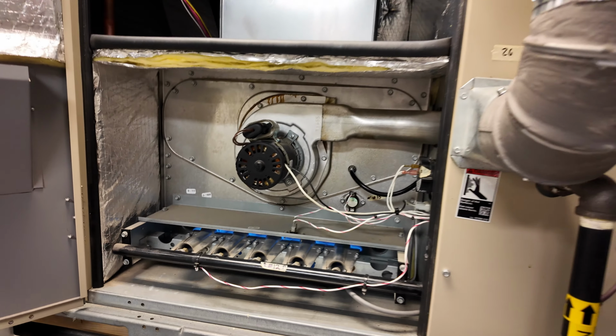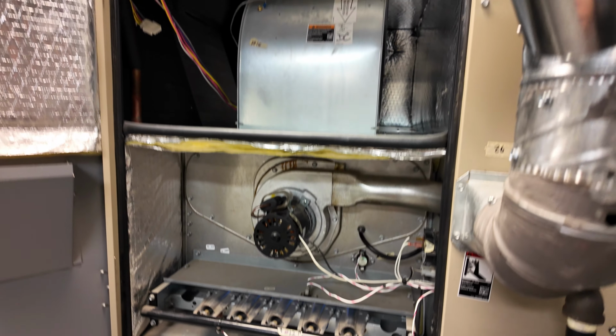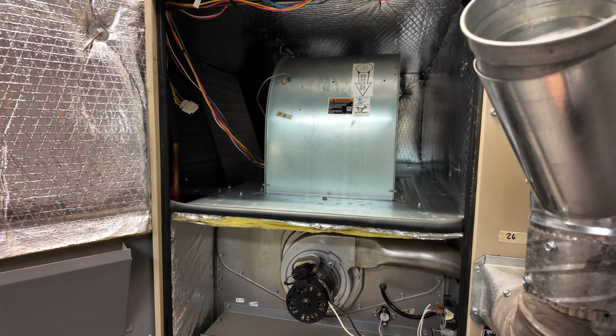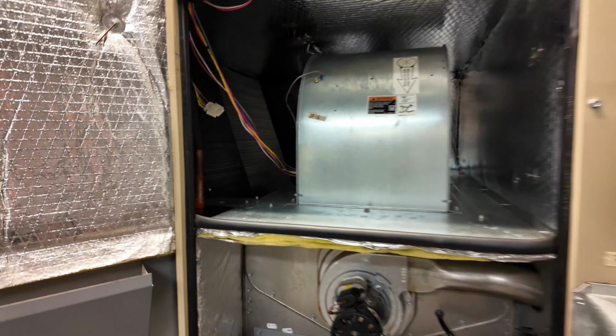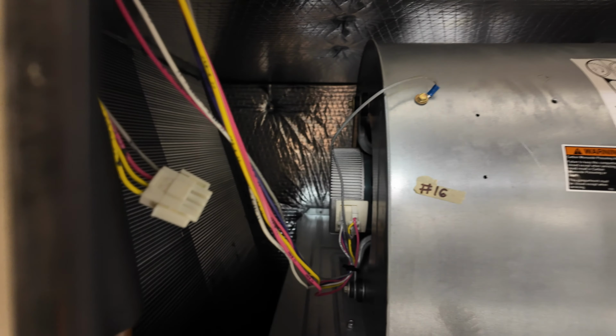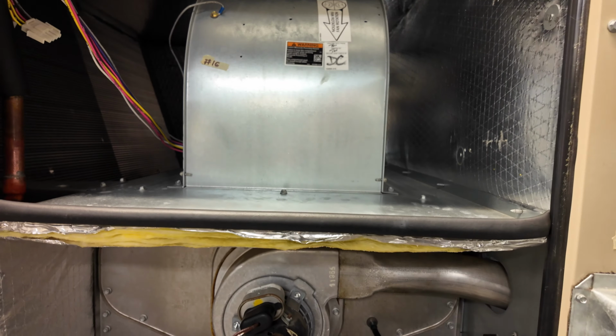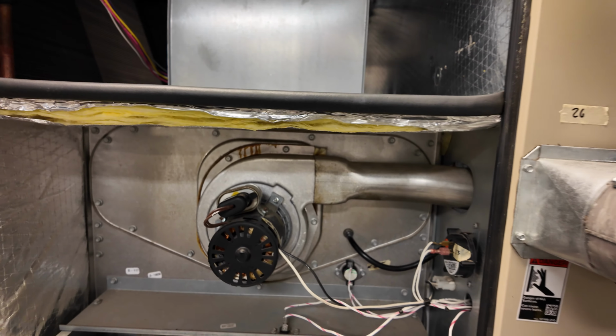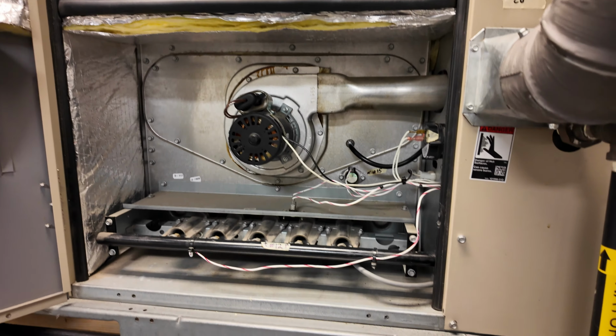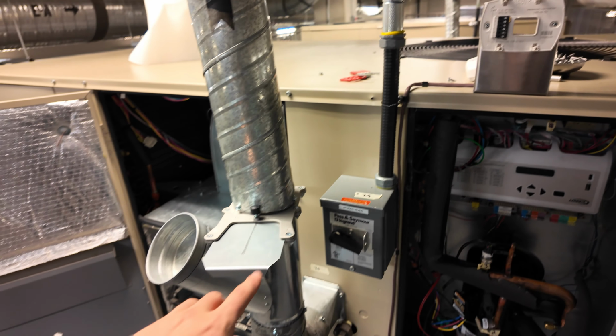And then we will have our heat exchanger start to warm up, and then after about 30 seconds or so, the blower will kick on. This is an ECM blower on this unit, and now here we'll just cycle through that process again. Just going to turn the unit off.